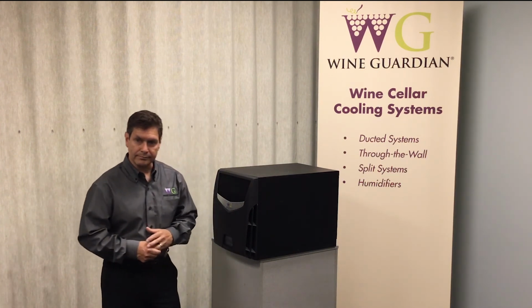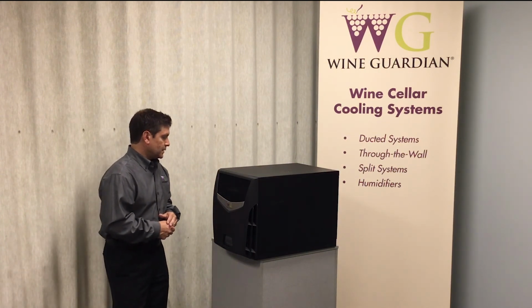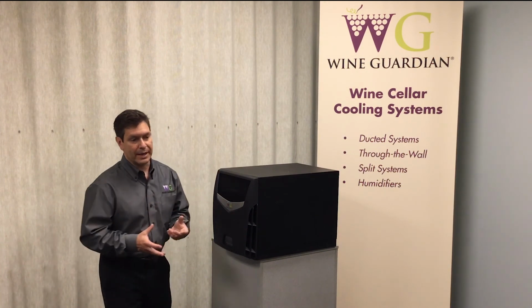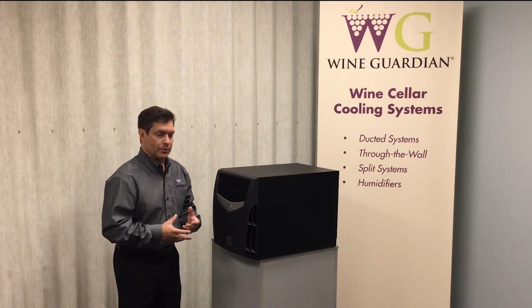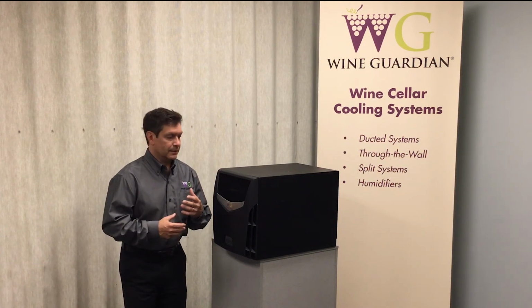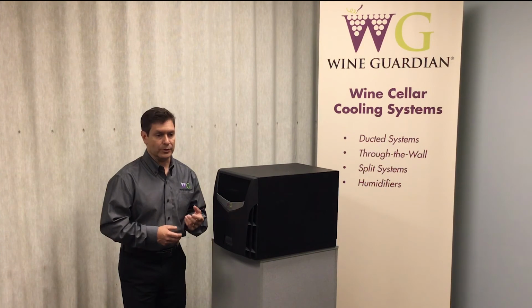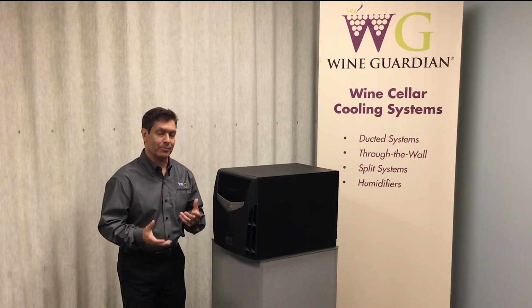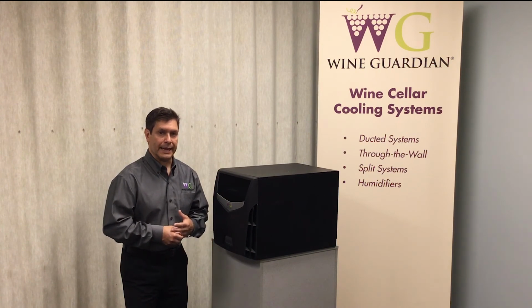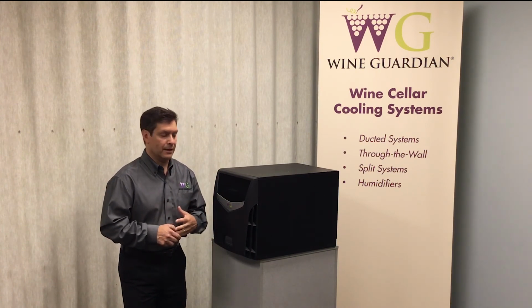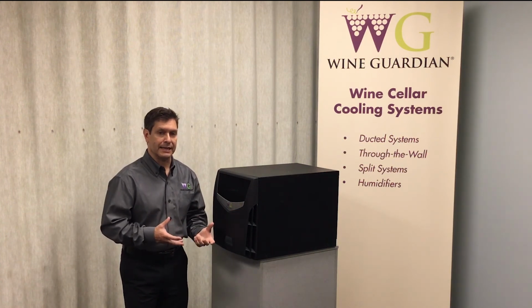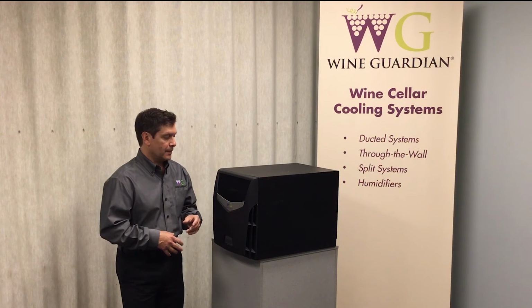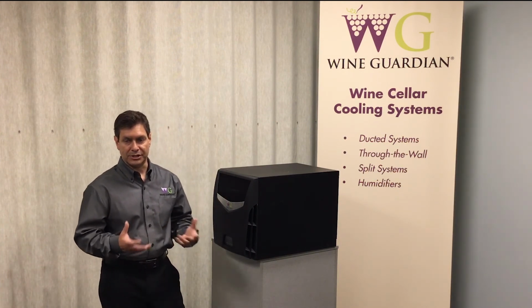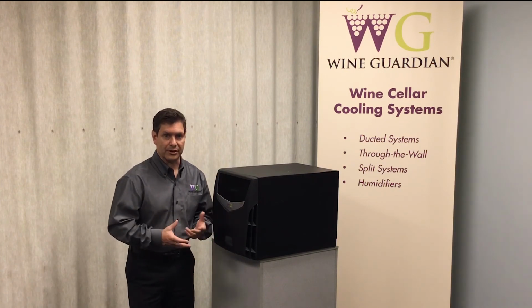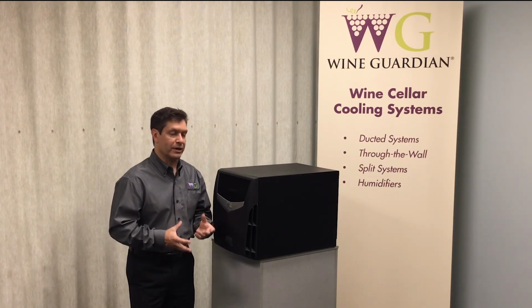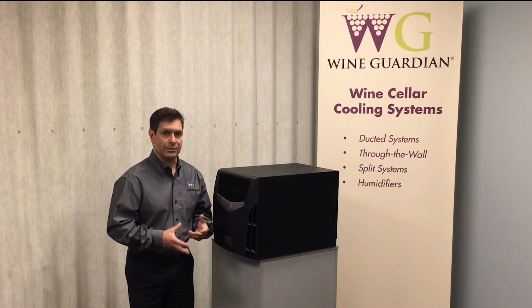Do you recommend we attach a drain to the unit? That's a good question. What we recommend is that upon initial startup, you turn the system on, connect up a drain to the unit. We provide a plastic drain hose. Connect up a drain, maybe bring that drain to a bucket, and let it operate for maybe a week or two to see how it functions. Are you getting any condensate out of the unit? Maybe you run a little bit longer than that, depending on the time of the year that you're starting up your wine cellar and the humidity levels you're starting with in the space, just to see how the unit is operating and if that condensate removal system has the ability to keep up with it.